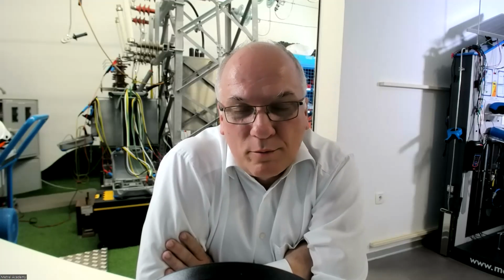You need a big volume of battery, which is atypical for handheld instruments, and it's simply technically not possible to realize something like that. You would need quite a big accumulator to make a measurement with this instrument on a big transformer with the battery. That's why you have only the public power supply, an external power supply, not battery driven.